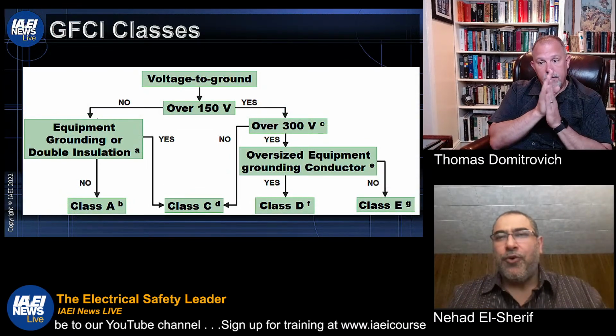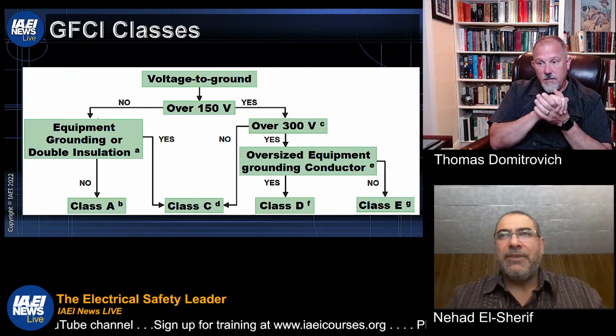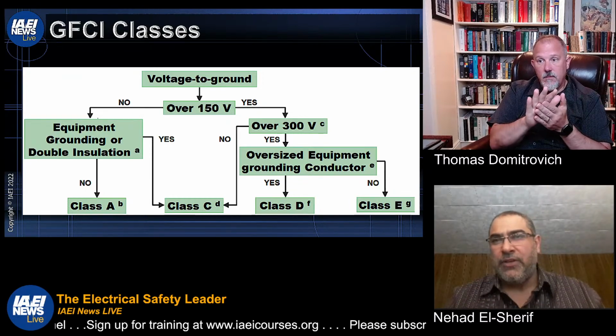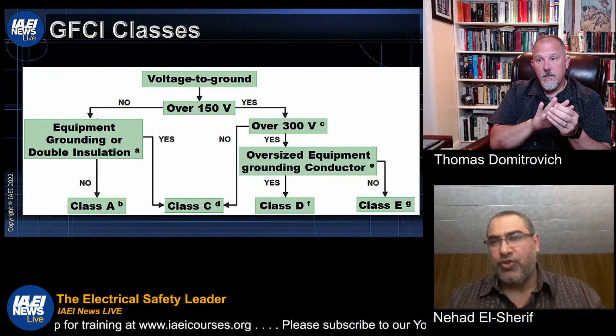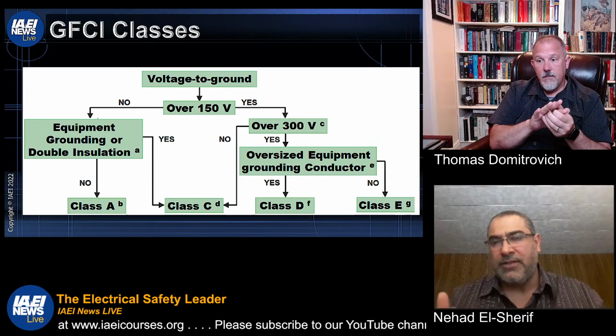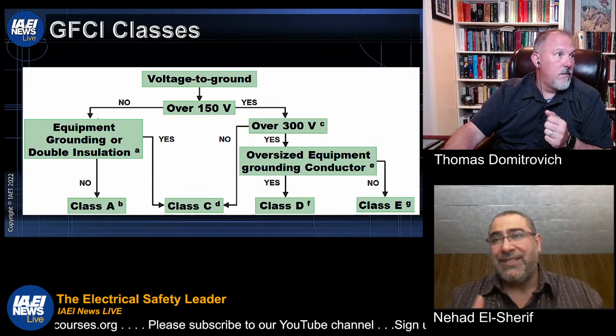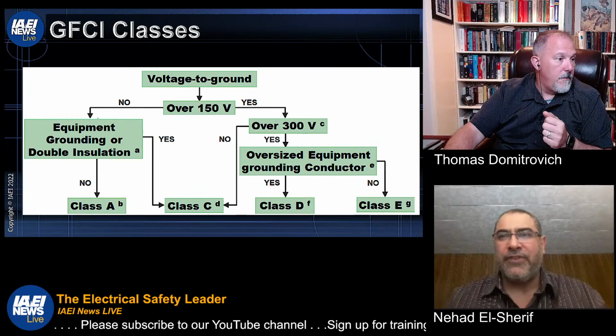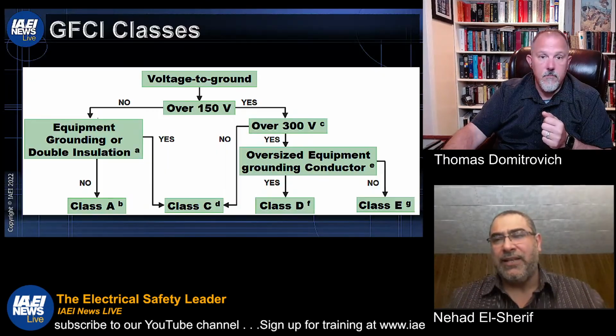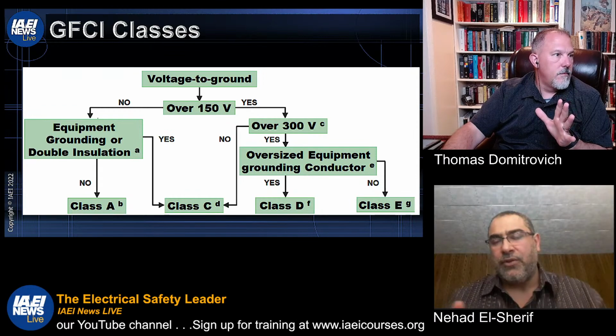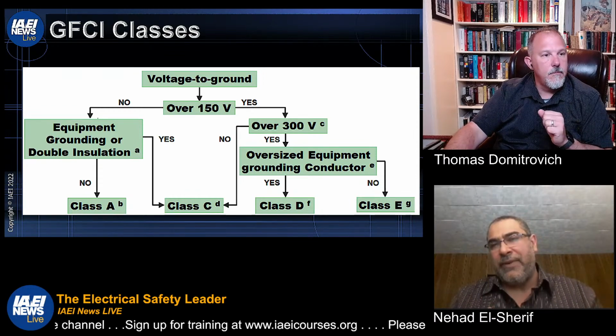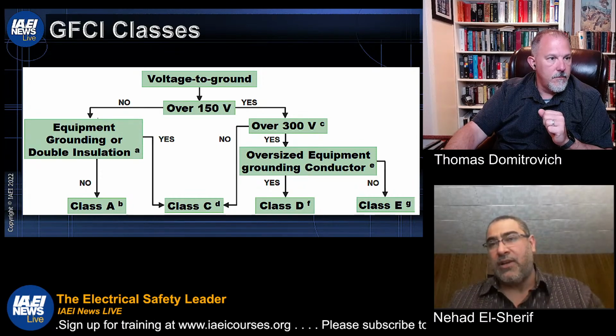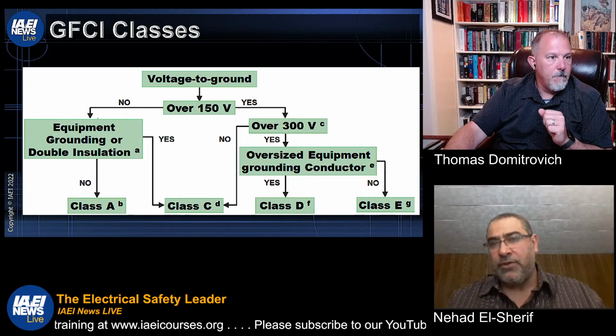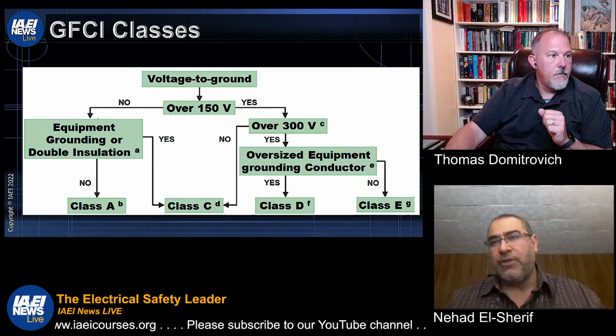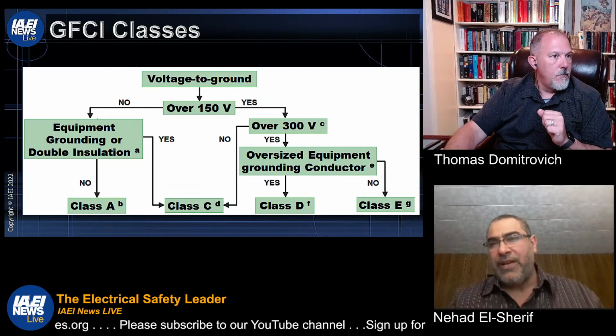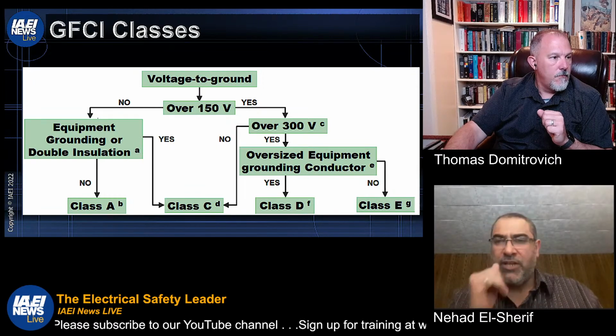I guess this is where hopefully we are able to clear the misconception or confusion between the different classes. And it just starts with the voltage to ground. This chart is adopted from the UL 943C outline of investigation, not a standard, which defines Class C, D, and E. This is where you can figure out whether your application requires a Class A, Class C, Class D, or Class E. It all starts with the voltage to ground. And like the definition said, if the voltage to ground is over 150 volts, then you're getting into the special purpose area, Class C, D, and E.